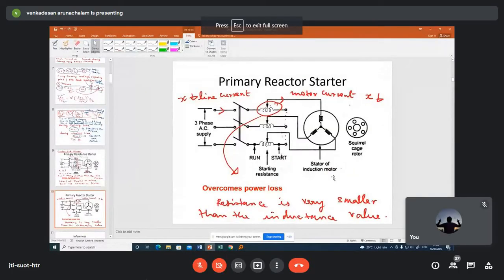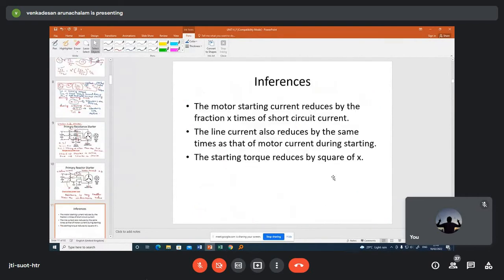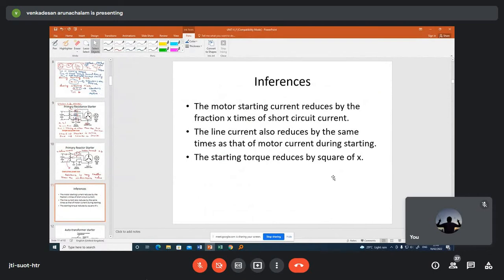It's a very simple starter. Only some resistance is added and a reactor is added. So that is the primary resistance starter and primary reactor starter. So from these two starters, what do we infer? The motor starting current reduces by a fraction X times the short circuit current, because some fraction of the resistance or some fraction of the reactance or inductance is being added to the stator winding.